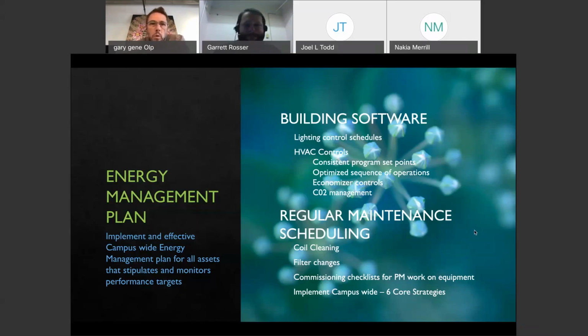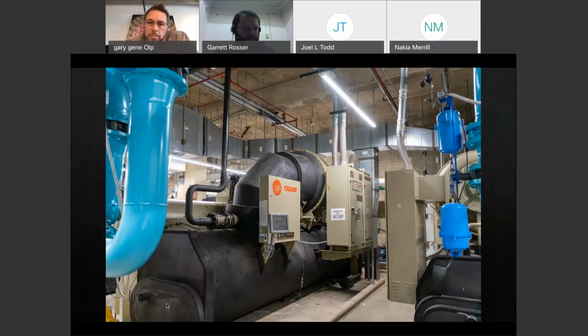One thing I'll mention as we move to the next slide is CO2 management. It's primarily to control the quality of fresh air. If you've been in an auditorium or classroom designed for 165 people with only 5 people in there, everybody's freezing. That's because buildings are designed with a CFM fresh air requirement per person that has to be provided to that space. Most engineers design that fresh air makeup for 165 people with no controls to drop it down when there are only 2, 3, or 5 people in the room. That's what CO2 monitors do: they monitor the amount of CO2, and if fresh air isn't needed, it's not generated. So you're not using energy to create conditioned air for 163 people who aren't in the room.